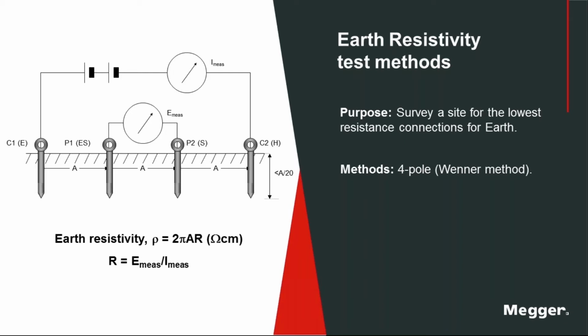Some of you have probably already recognized this as a Kelvin bridge, which is also used in other types of electrical test instrumentation besides grounding. It has 2 current terminals on the outside that inject a test current. In ground testing, it's a square wave, because you want to avoid the noise that's in the soil.